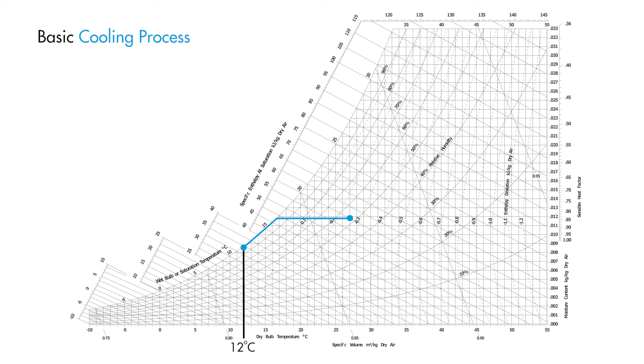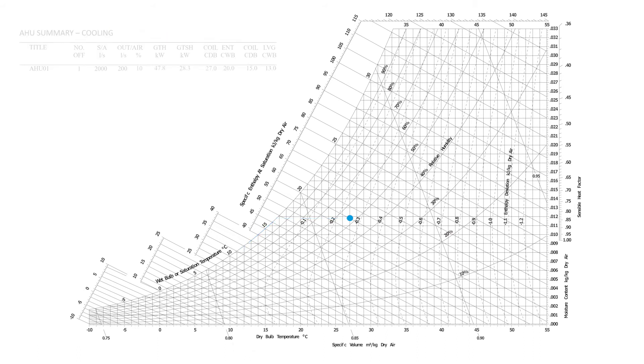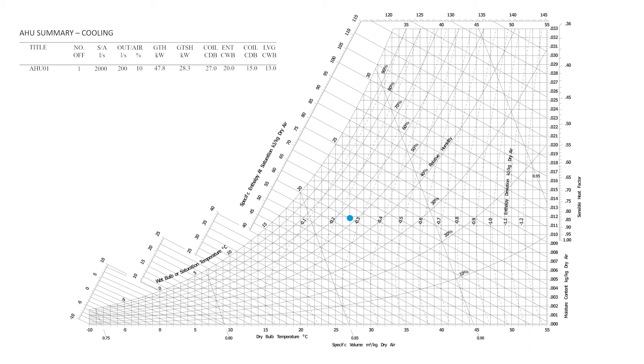Well remember how I said that understanding the HVAC process in some situations is important? What if we had the same air on cooling coil condition of 27 degrees dry bulb and 20 degrees wet bulb, but this time a heat load calculator states that we need a supply air temperature of 15 degrees dry bulb and 13 degrees wet bulb in order to satisfy the sensible and latent cooling loads?